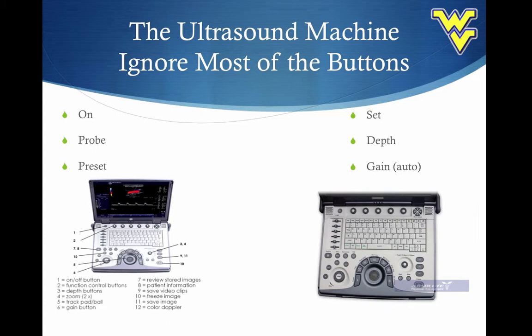There's 2 buttons that you really have to know how to work a little bit and manipulate, and they're pretty easy too. So there's a depth key or switch or toggle, and on these machines it's right over here, and it's a knob. You turn it counterclockwise to decrease the depth, clockwise to increase the depth. But that's going to be important, and that's something you have to adjust fairly regularly when you're doing ultrasound. And there's the gain. The gain is just the overall brightness of the image on your screen. It's like turning up the volume on your stereo. When you turn the gain up, the intensity on your screen increases, so everything looks more white. As you turn the gain down, everything looks more black.